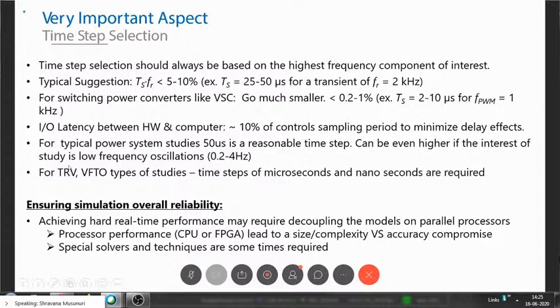Like if you take TRV or VFTO studies. TRV stands for transient recovery voltage. It is the voltage across a breaker when the breaker starts to open because of a fault or something. There will be an initial transient across the breaker, and then it slowly dies down. The extent to which the peak of the transient goes and the settling time of the transient determine the stress on the breaker. That is very important for the OEMs, the original equipment manufacturers of breakers. In TRV studies the transient is in the range of kilohertz, so it's not possible to capture it if you are running at 50 microseconds. To effectively capture it, you have to go as low as 2 microseconds or 1 microsecond.